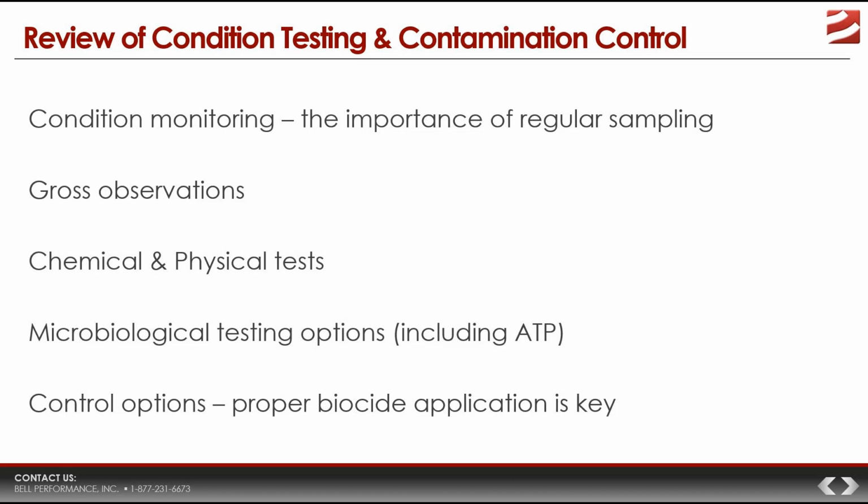What's the condition of your stored fuel like? And does anything hint that you have a current or a future problem? Things like gross observations, sight and smell observations, are a good, easy starting point. Even though they're not intended to be fully quantitative, they do have definite value. You have chemical and physical tests that give us ASTM-rated measurements of specific fuel properties that may be important for telling us the current state of the fuel as well as being predictive about whether there might be a problem with the fuel that's coming.